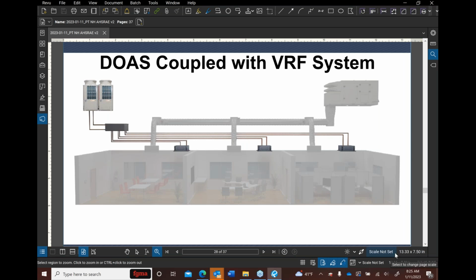In this particular case, as you saw from the picture before - and there'll be a picture coming up that shows the roof - we have multiple dedicated outside air systems to serve up to about 3 classrooms each, and that's to keep our duct sizes lower and our static pressure losses lower.